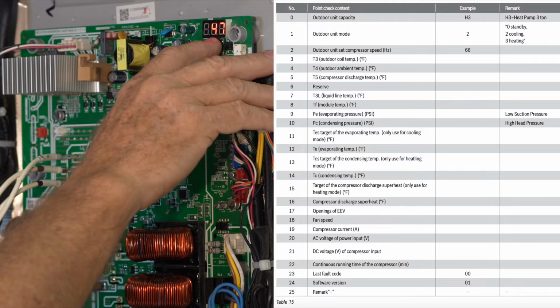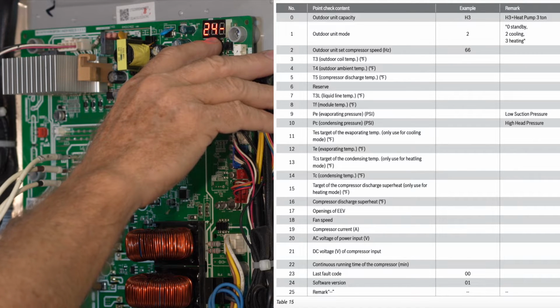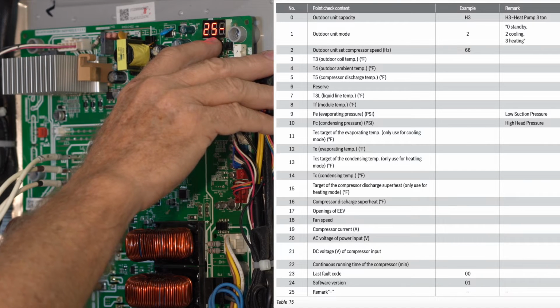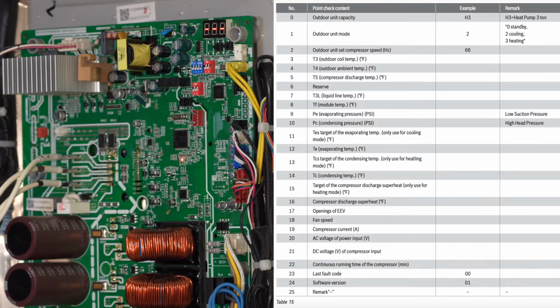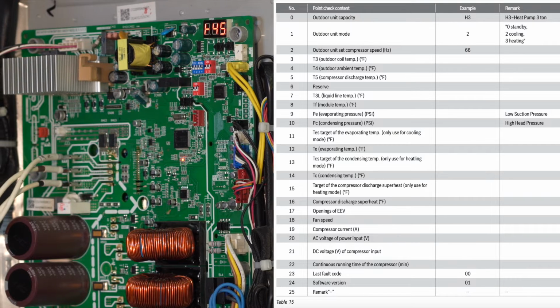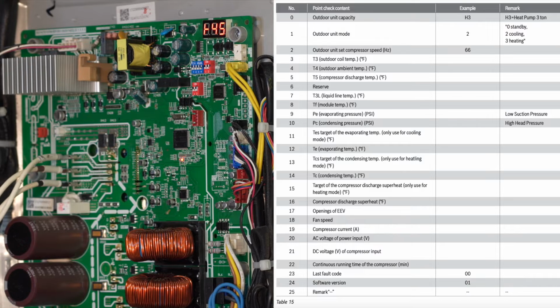24 is 47. And 25 is dash, dash, dash. Okay? Now, it's as simple as that, doing a maintenance, doing a service call, and if I take these numbers, and again, they mean something, and it would be really great for us to have those numbers in a technical call. It would be great to have those numbers in a maintenance call. It would be great to have those numbers in a commissioning of the unit for the very first time to get a baseline of what this machine is doing.